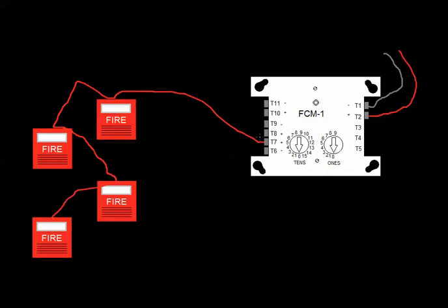I'm going to switch to the pen. I think it's faster. And you still have an end of line resistor. And when your panel is clear, when this control module is not on, through programming, it's not being told to be turned on, it works the same way. Your power essentially is what's flowing through the circuit, through the end of line resistor, and telling you that this module is clear.